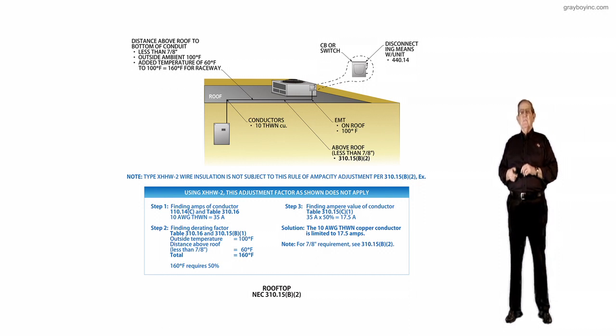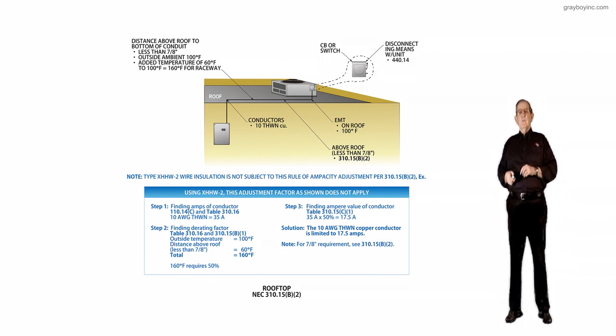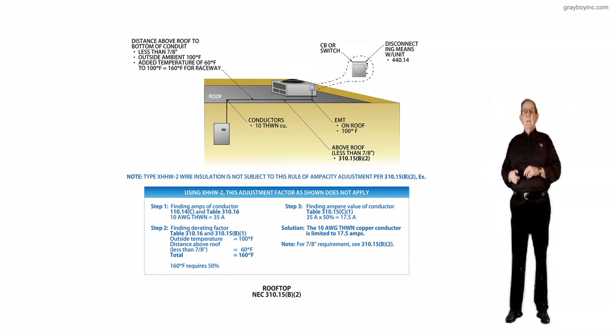Finding the derating factor from table 310.16 and 310.15B1, the outside temperature on the roof is 100 degrees Fahrenheit from the ASHRAE book. The distance above the roof is less than 7 eighths of an inch, so 60 is tacked on, and the total would be 160 degrees Fahrenheit. That 160 degrees Fahrenheit from your table 310.15B1 is 50%. So your conductor just dropped 50% in ampacity.